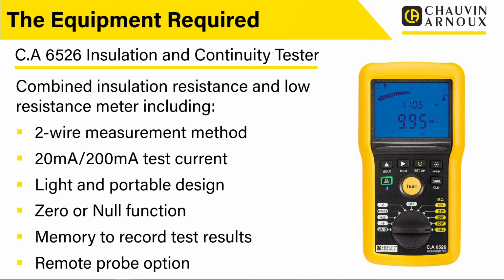So it's a 2-wire measurement method. It uses either a 20 milliamp test current or a 200 milliamp test current. It's light and portable, so it just fits in your hand. It's hard to see the scale of it in here, but it's sort of multimeter size. It's got the option to zero, so you can zero off your test lead resistance. And it has a memory, so you can record the results that you've obtained. There is also, which is very useful, a remote probe option. I know a lot of people like those when you do measurements, so you don't have to balance 3 hands and hold something in your mouth at the same time. You can use the remote probe to do the tests.